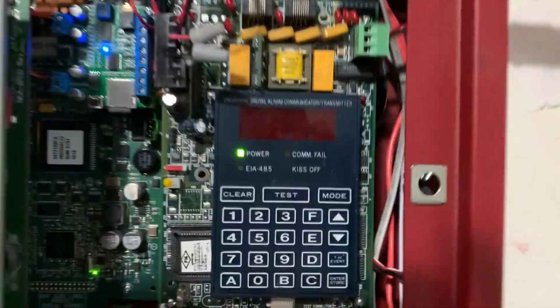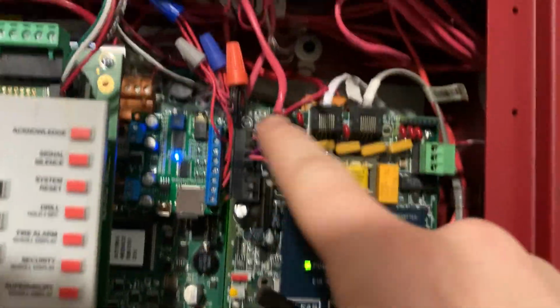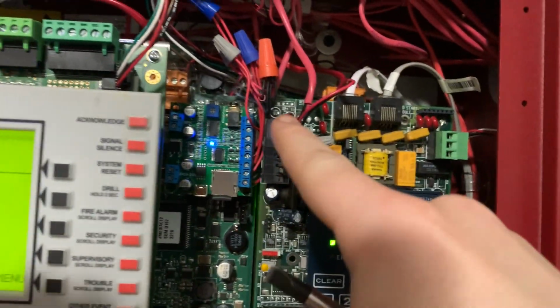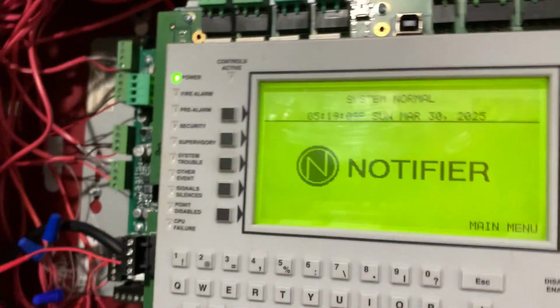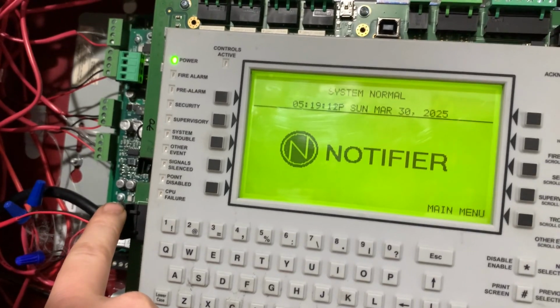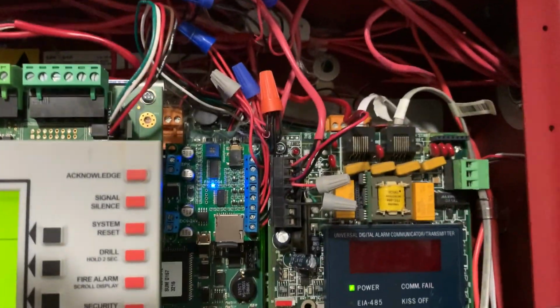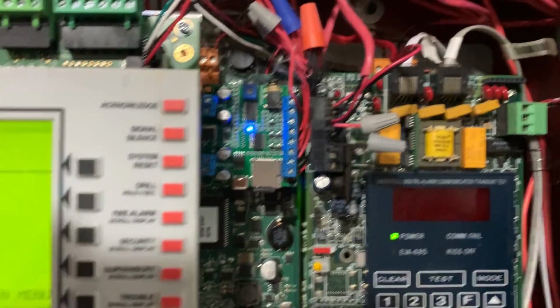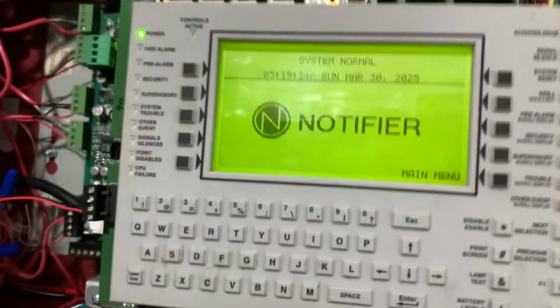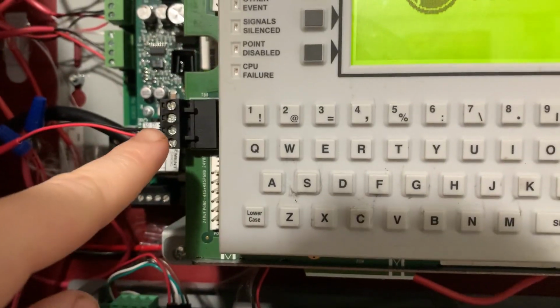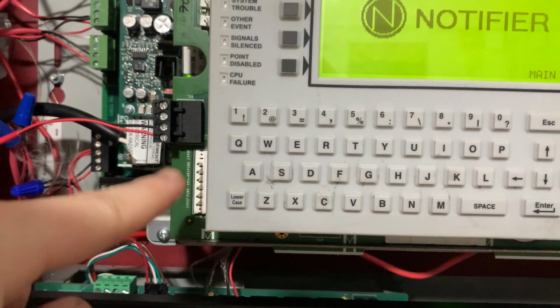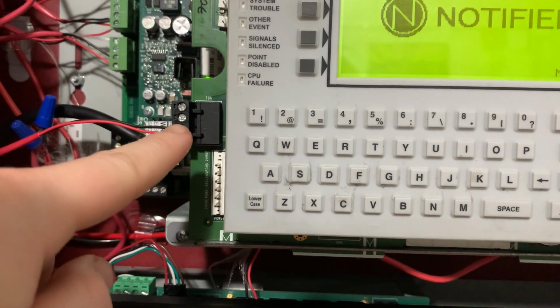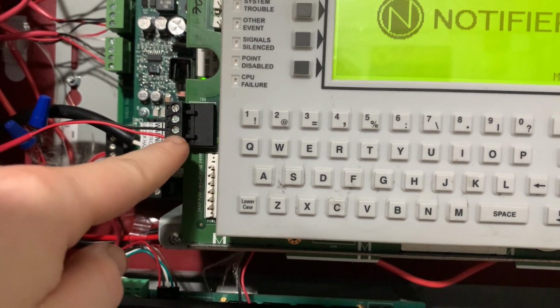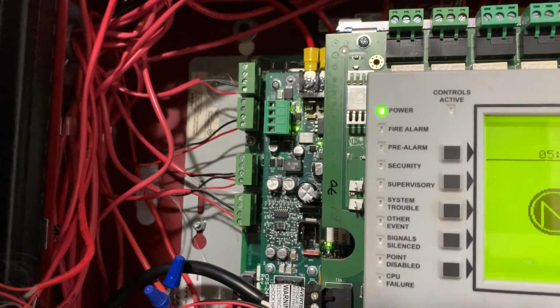If you open this up, you see here we got our UDACT, which is being powered by my panel's non-resettable power. But by code it's supposed to be powered by the output power right here, but I just have it powered by my panel's non-resettable power. Anyways, here's the inside of it, and here's the power connections. I do not have a power clip for the NCA-2, so I have to power it using the 24 volts in terminal right here. Here's still the wiring for the NFS2640.